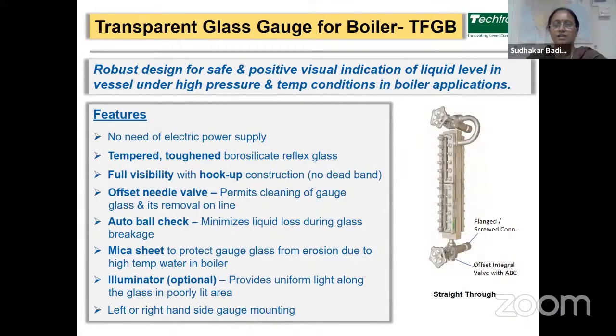The next one is a transparent glass gauge, that is TFGB. This is also a robust design for safe and positive visual indication for liquid level under high temperature and high pressure applications. Similarly, this also doesn't require any power supply. The glass is tempered and toughened borosilicate glass. Sorry, this is a transparent glass, not reflex. Again, you will get full visibility with the hookup construction, that is no dead band. The offset needle valves are provided to permit cleaning of gauge glass and its removal online. The connections will be flange or screw connections.